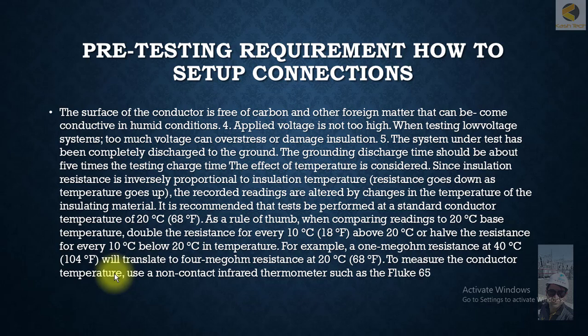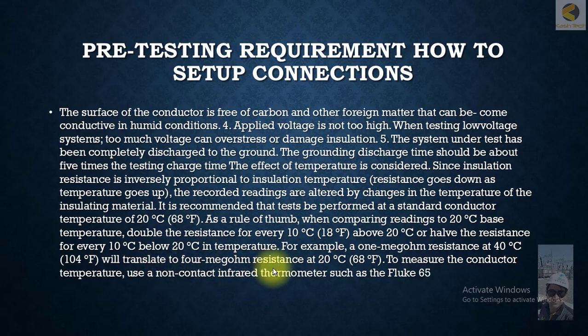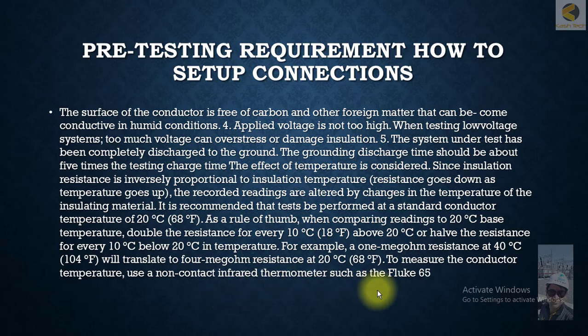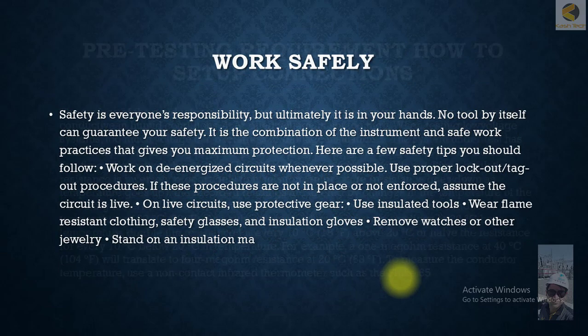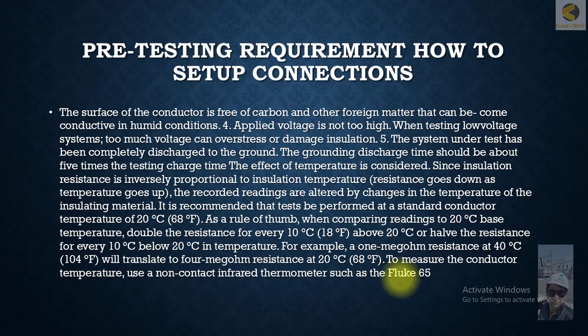As a rule of thumb when comparing readings to a 20-degree base temperature: double the resistance for every 10 degrees above 20°C, or halve the resistance for every 10 degrees below 20°C. For example, a 1 megaohm resistance at 40 degrees Centigrade is equivalent to 4 megaohms at 20 degrees Centigrade. To measure conductor temperature, use a non-contact infrared thermometer such as the Fluke 65.